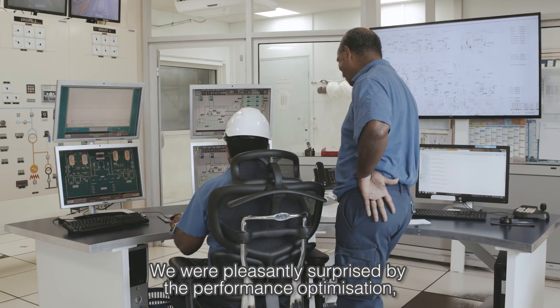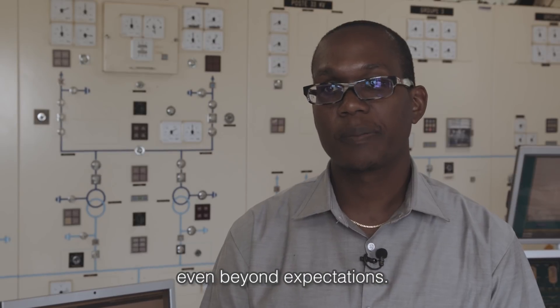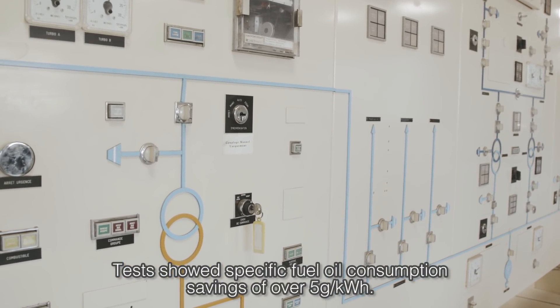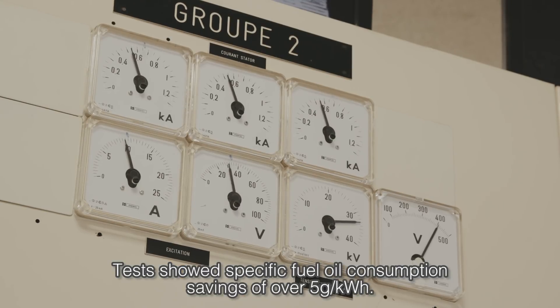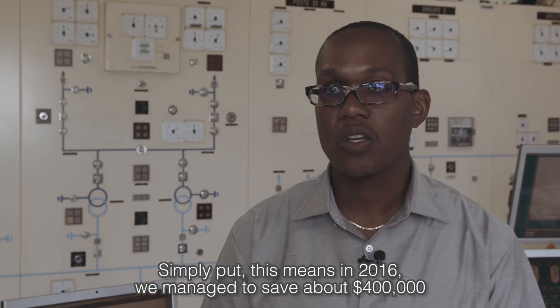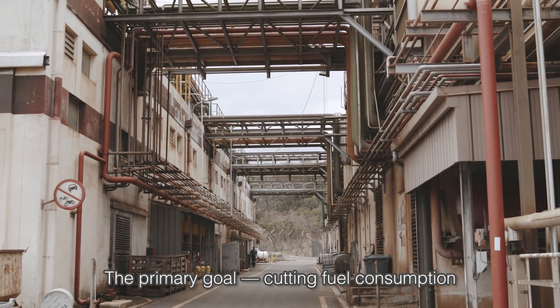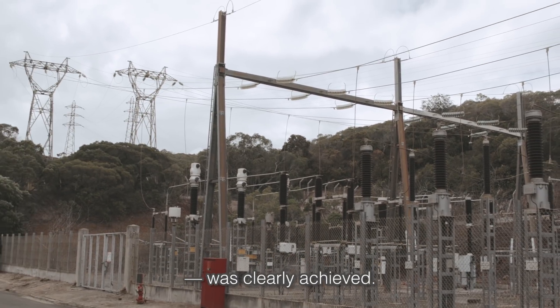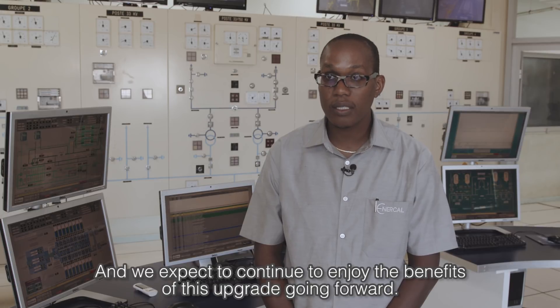We were pleasantly surprised by the performance optimization — even beyond expectations. Tests show specific fuel oil consumption savings of over 5g per kilowatt-hour. Simply put, this means that in 2016 we managed to save about 400,000 dollars, thanks to the performance optimization. The primary goal, cutting fuel consumption, was clearly achieved. And we expect to continue to enjoy the benefits of this upgrade going forward.